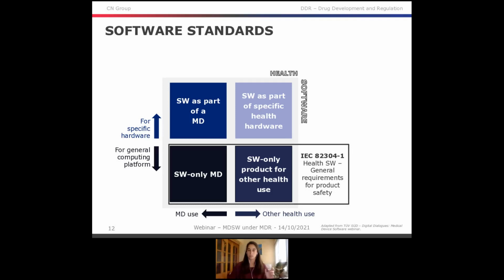So the first software standard, the IEC 82304, would cover the software related to general computing platforms, both the health and the medical device software. However, the IEC 62304 would cover only the ones related to medical device software, both the ones running on medical devices and the ones running on computing platforms. As we can see, health software that is running on specific hardware is not covered by these standards. But if we have medical device software, we are going to have to consider both standards.